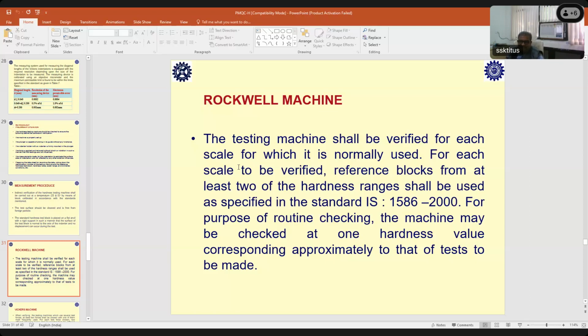But sometimes you may not have all the blocks, but in very few cases it is accepted. But the testing machine has to be verified for each scale for which it is normally used. So that is the requirement. Suppose we are using it for the A scale, you get the standard block for the A scale and verify whether it is giving the exact reading, or whatever the error is, you should have some way of compensating. For each scale to be verified, reference blocks from at least two hardness ranges shall be used as specified in the standard. This is all given in the standard 1586. You can refer to the appropriate part, whether it's part 2 or part 3, and then just follow the procedure for verifying the machine.